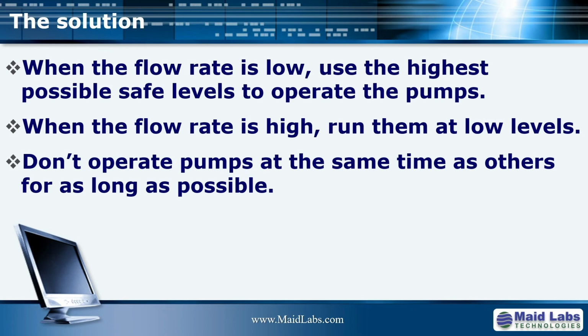When the flow rate is high, run them as low as possible. Don't wait to reach the lead level to operate your pump for 2 hours when the flow rate is high. Start the pump way earlier, so it will take more time to get to the lag level where both pumps start and the efficiency drops quite a lot. That's the solution. How to implement the solution?